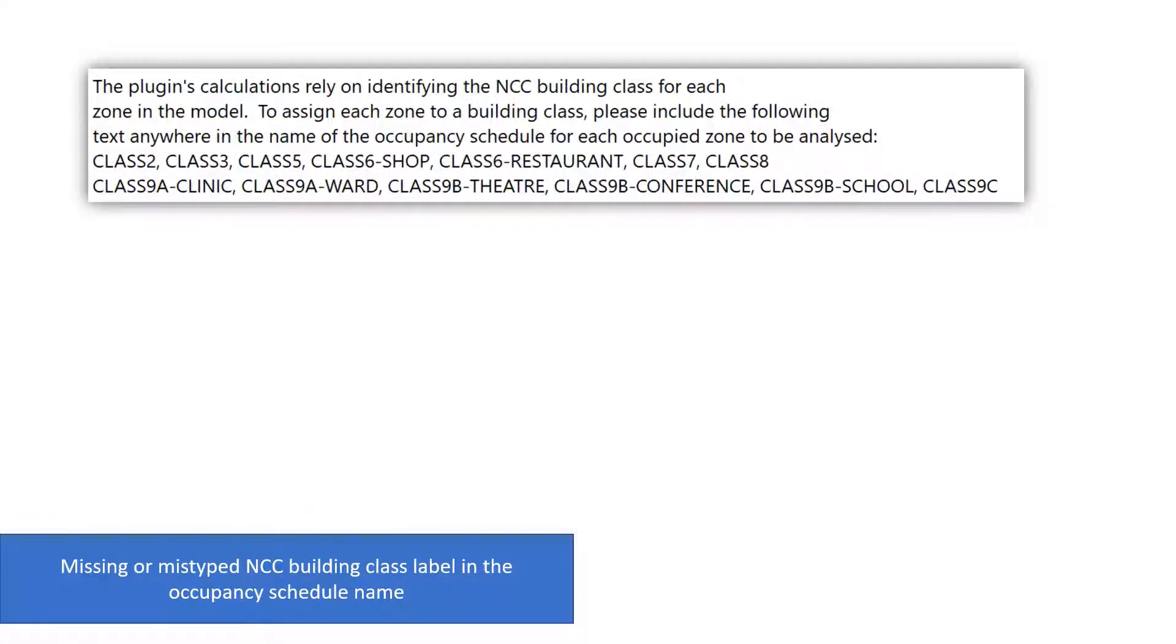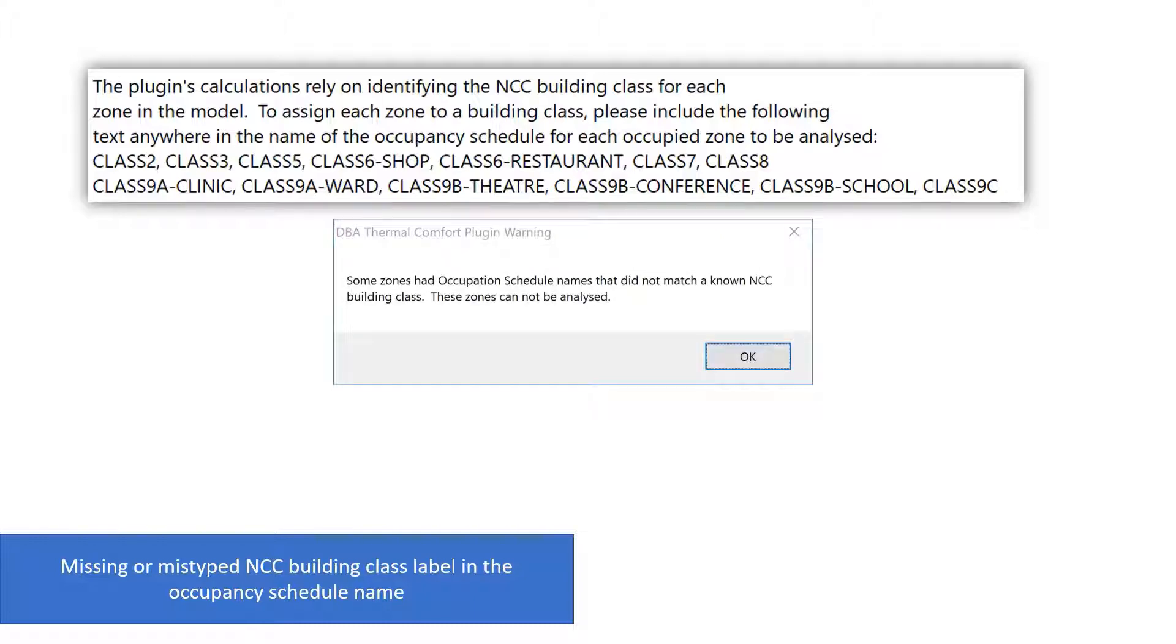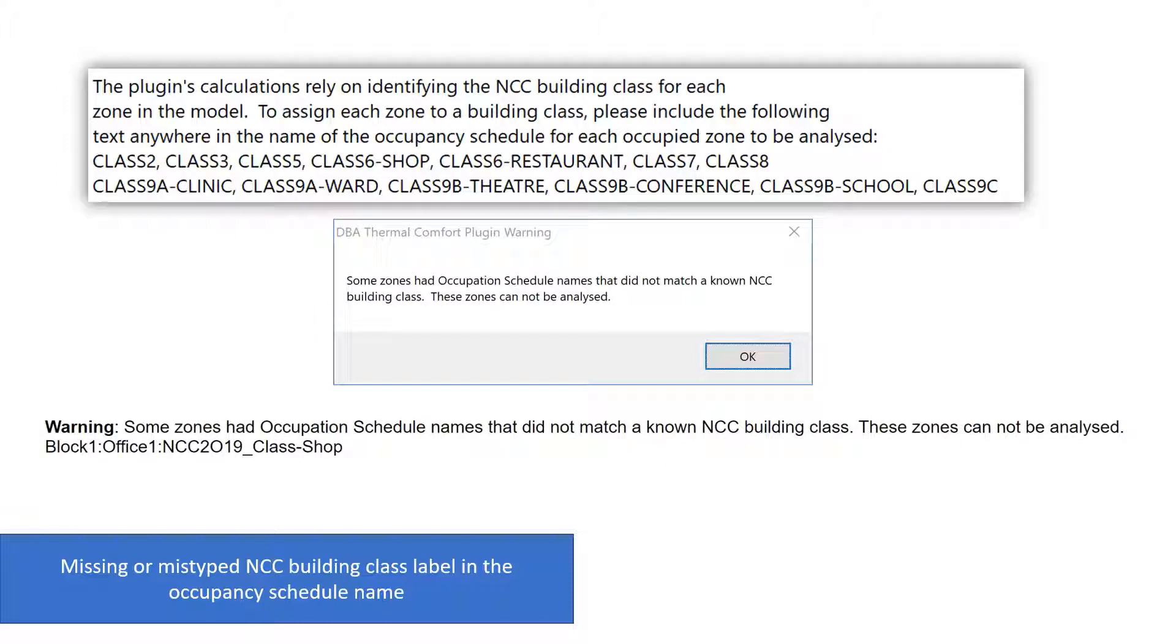All occupied spaces must have their NCC building class identified with a special label in the occupancy schedule name. If you missed some occupied zones when adding labels or made an error adding the label, you will get a warning that not all spaces could be analysed. The report will list all the occupied zones where building class could not be identified from the schedule name.